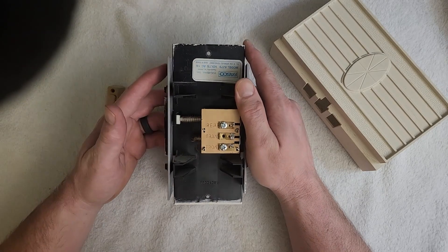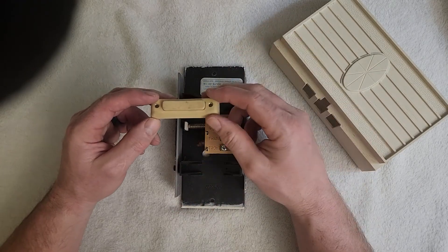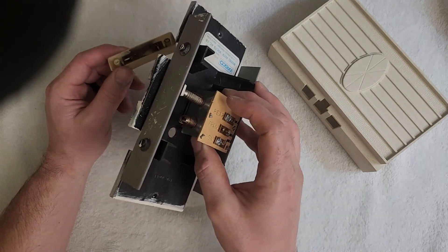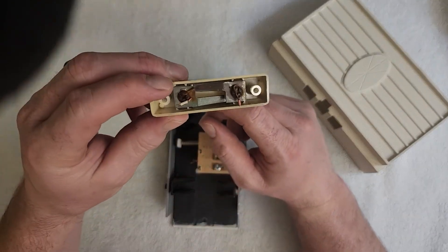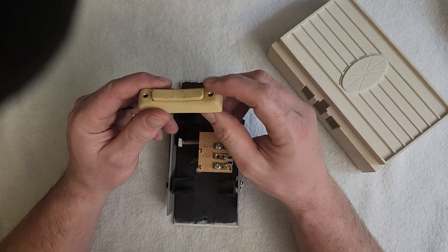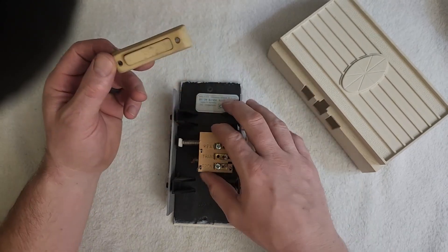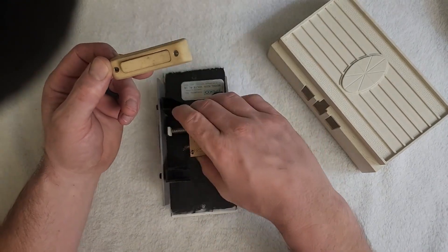There was no smell in the basement, but sure enough, this is what it was. I went to the switch and took apart all the components just to make sure something wasn't sending a call. I even disconnected the transformer — we're just going to redo the whole thing for them. I think this was the culprit: it just got stuck in there. You'll notice it's very rusted and corroded. I was able to get the switch stuck on the first try — it's now closed constantly, which would be constantly sending the call, locking this in, and forcing it to possibly get stuck after a period of time.